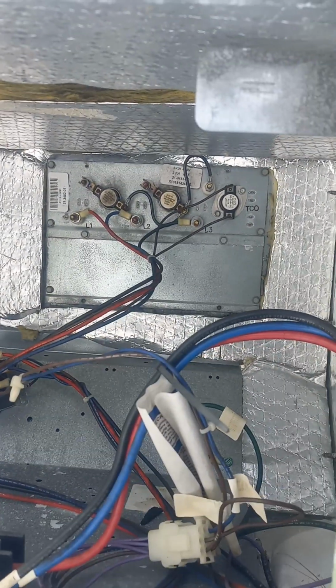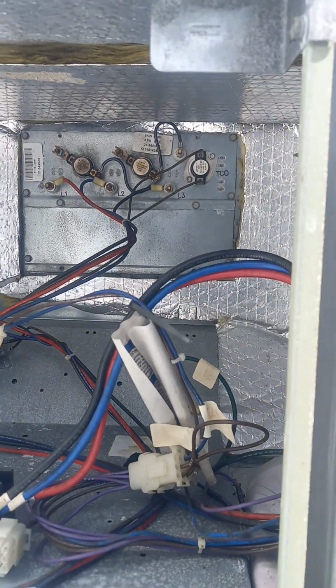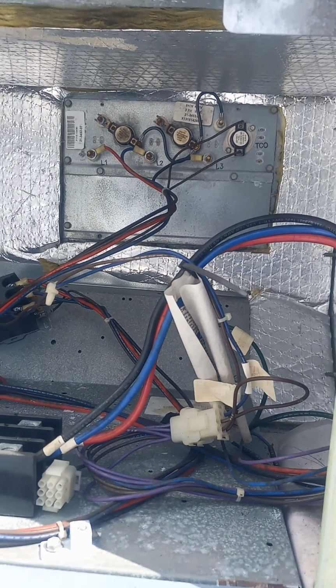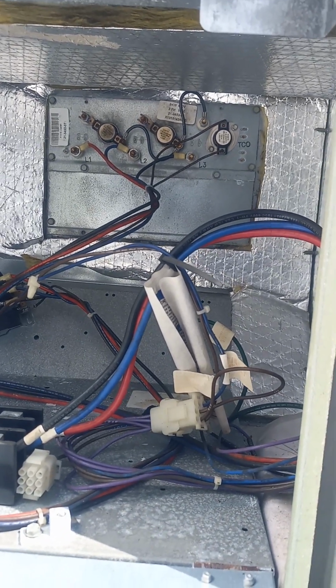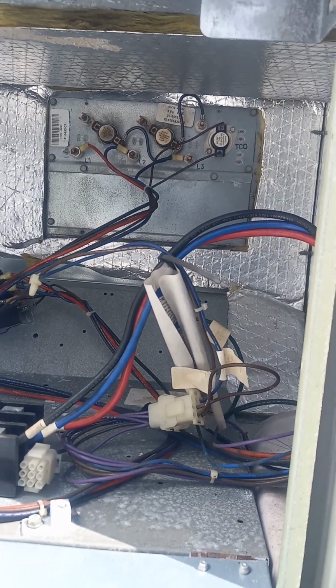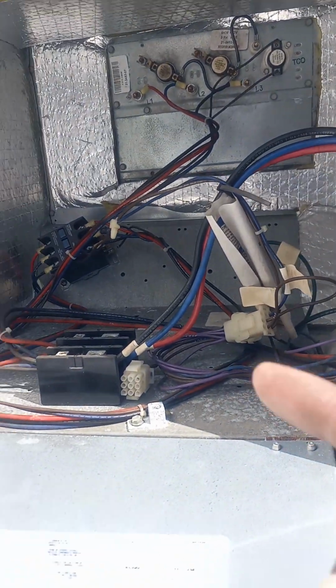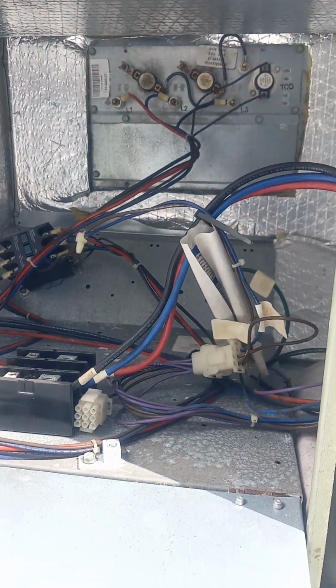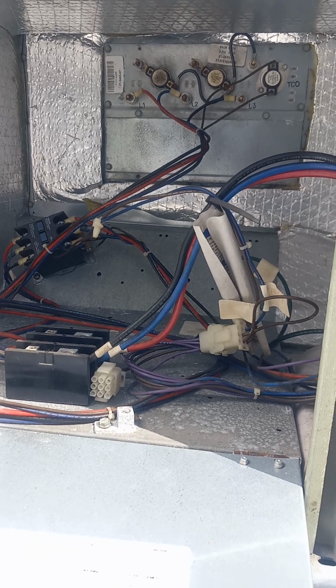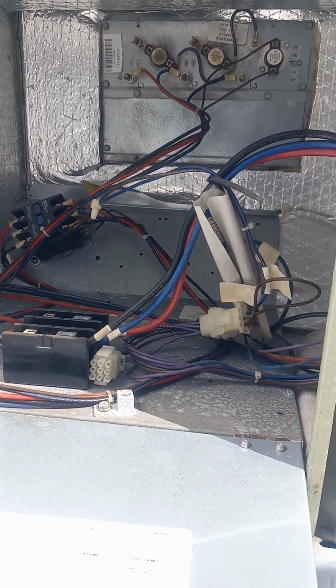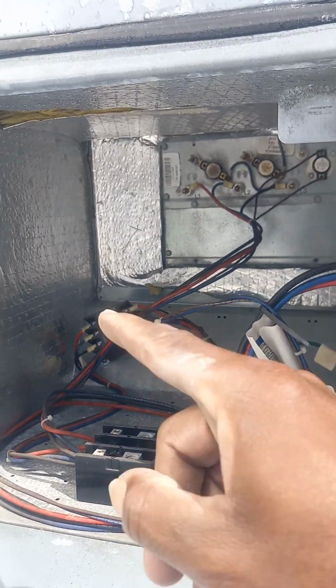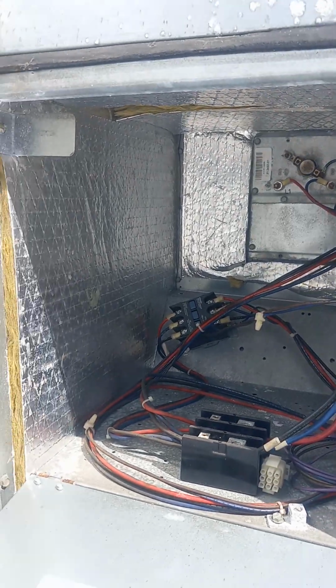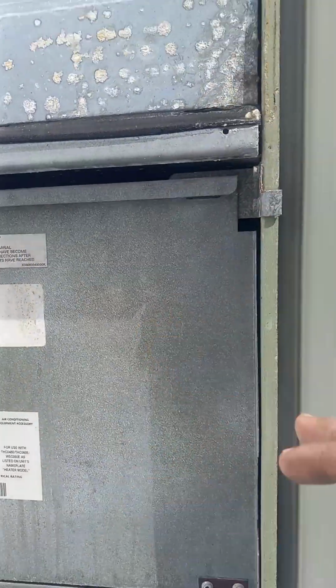That's the heater kit up there, and that's a 3-phase heater kit. So a 6 kilowatt 460 volt, and then you have a contactor that actually controls the heater. So that's operating. You have high voltage on one side, and the low voltage is what, when they call for heat, just throws that contactor over, and the contactor comes on and heats the space.